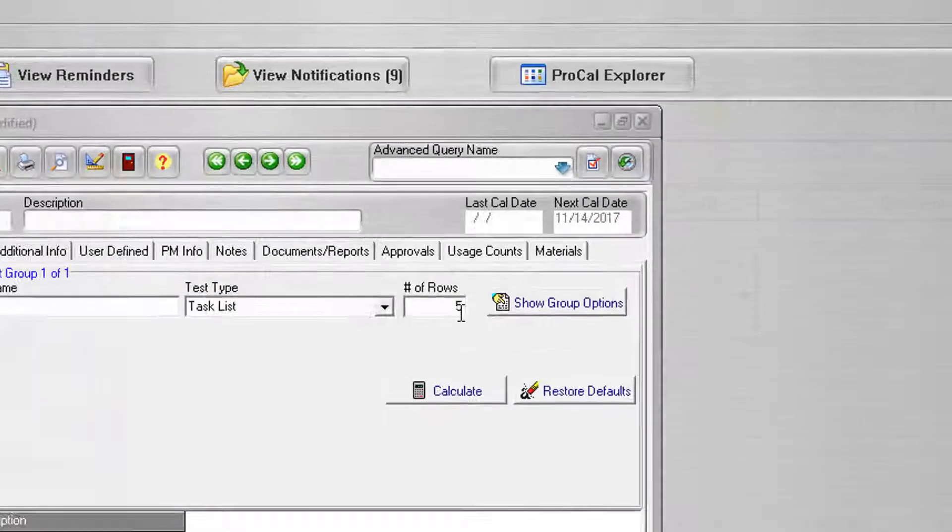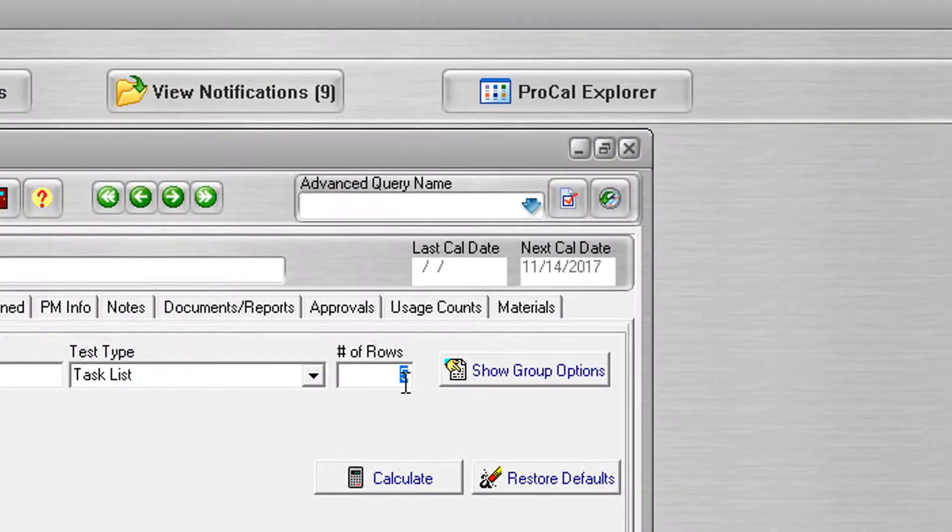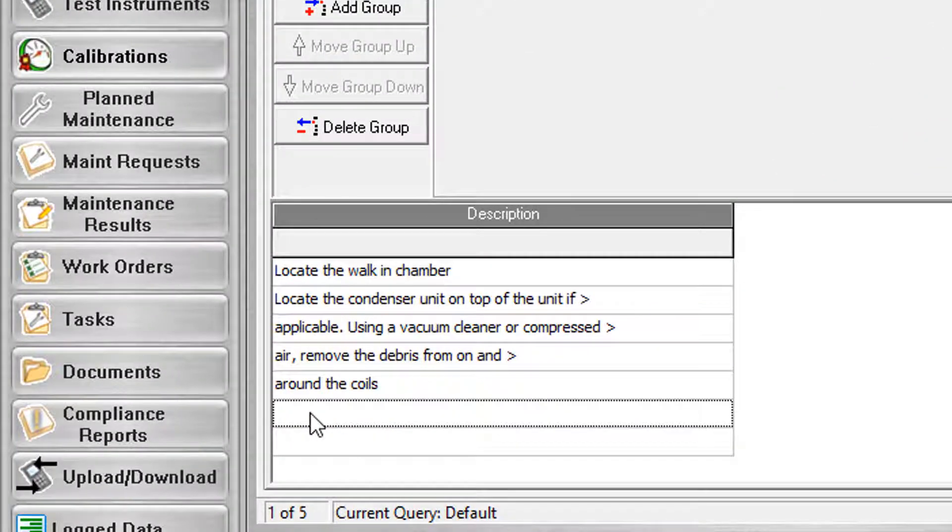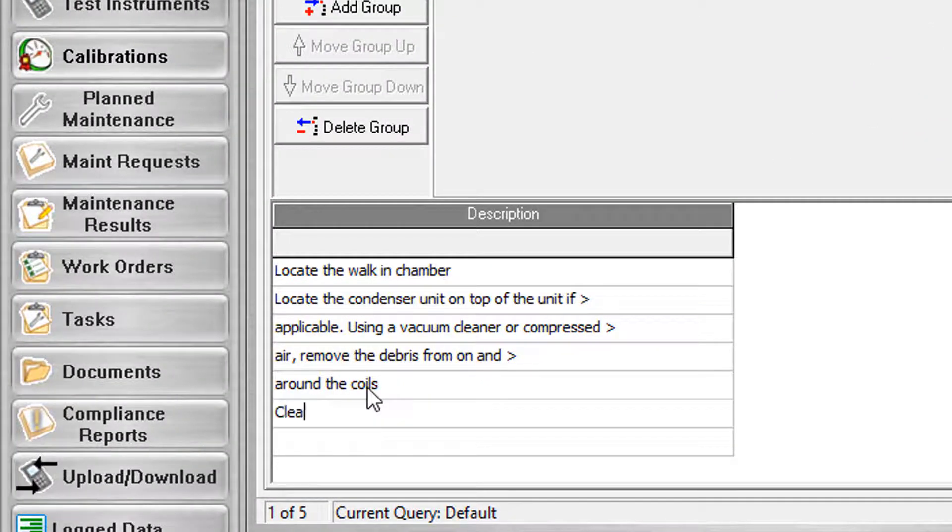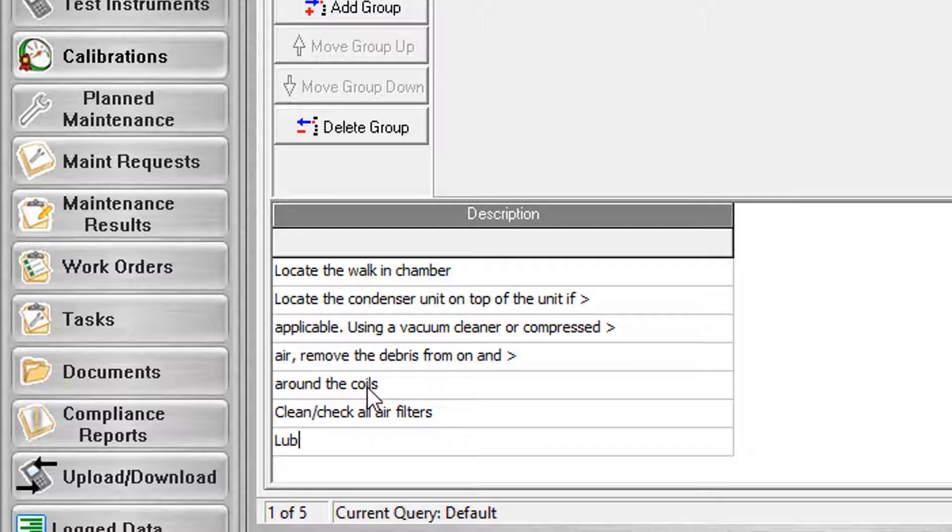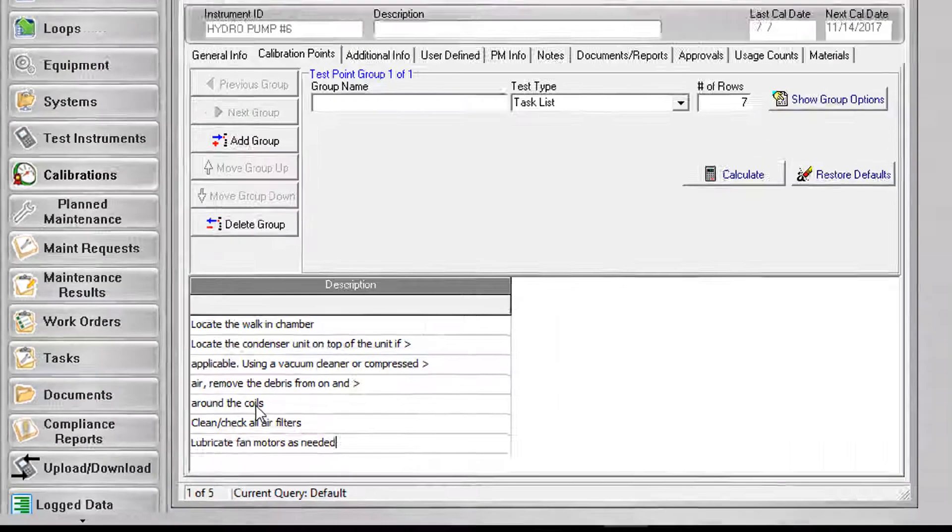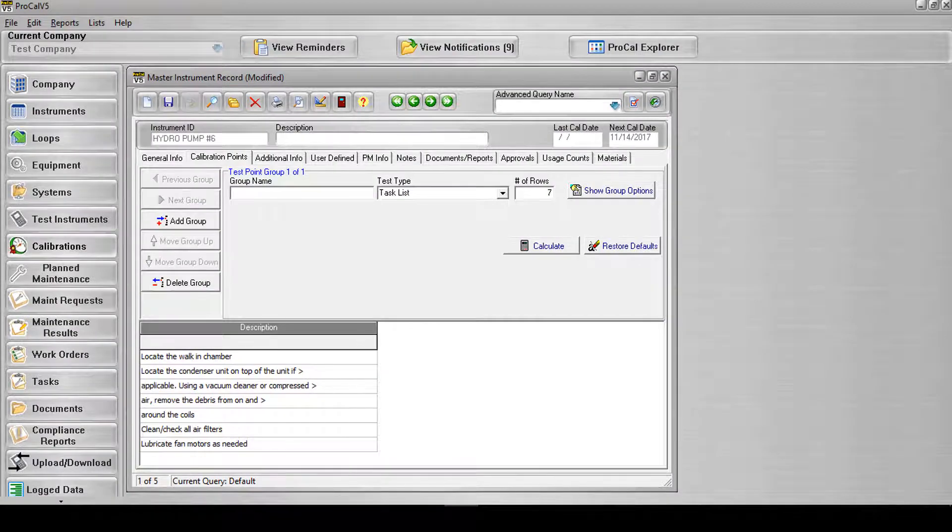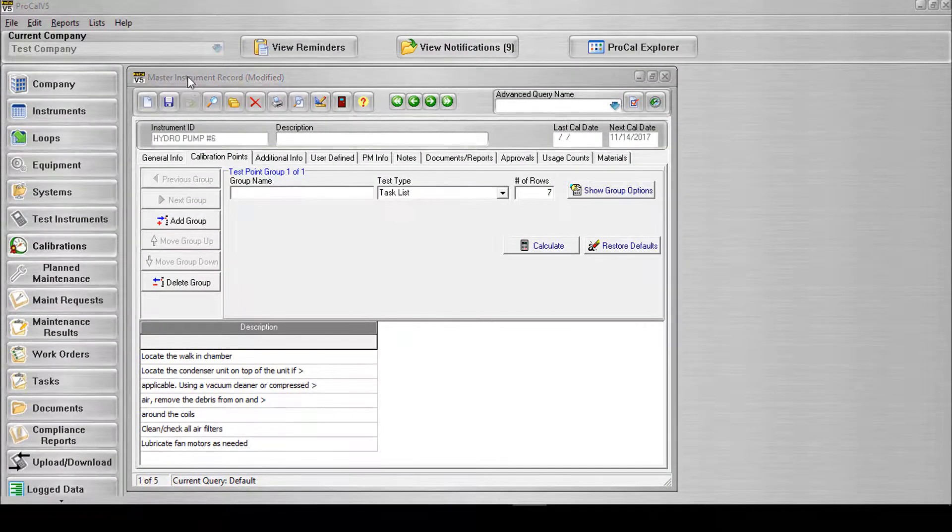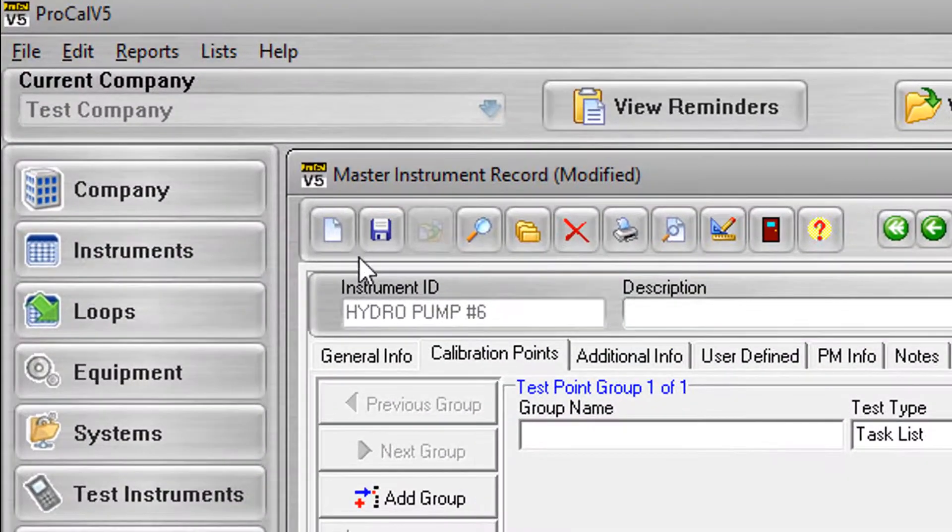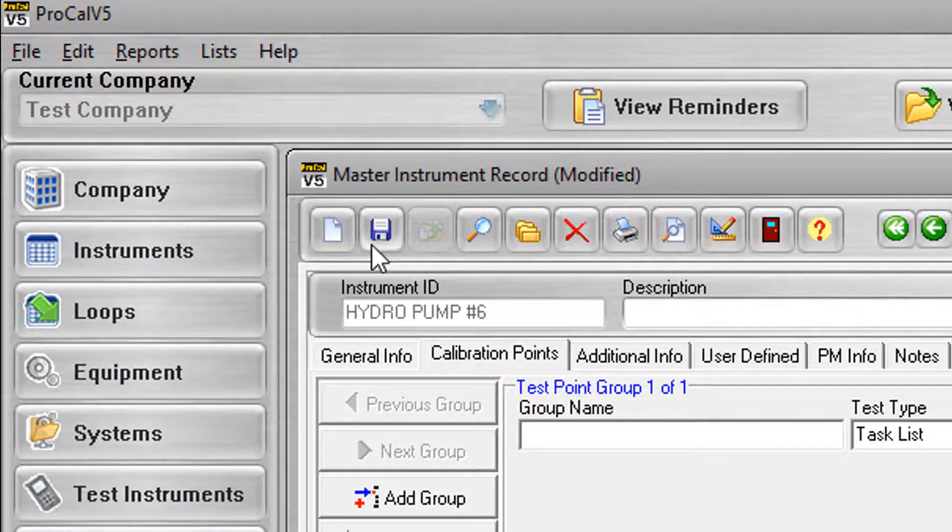The number of rows can be increased to increase the capacity of each step if necessary. There is no limit to the number of characters that can be entered using the greater than symbol, but due to restrictions from ProCal V5, only 255 characters will show on the calibration screen when the user presses the View Enter button. Once all of the relevant data has been entered, you can save the record.